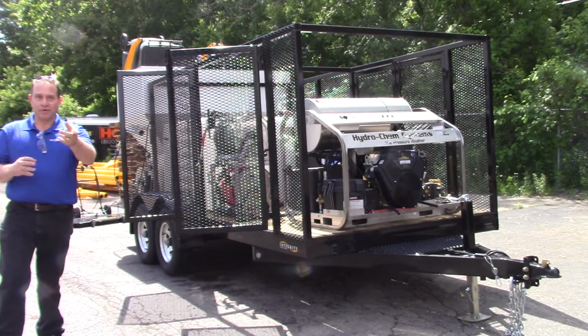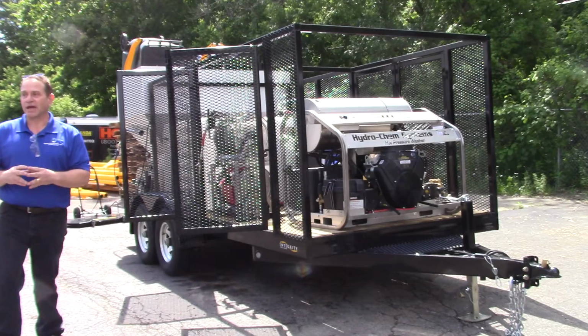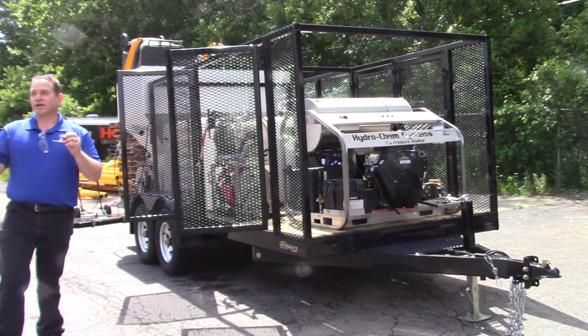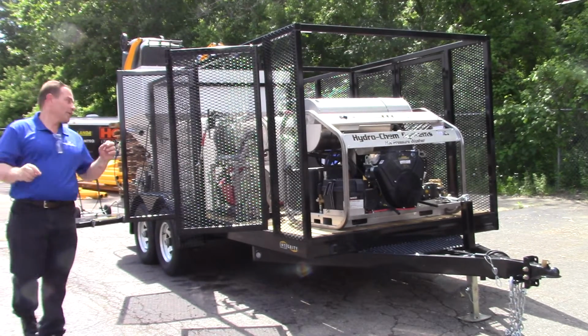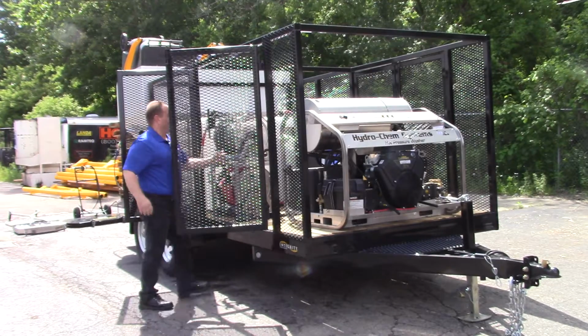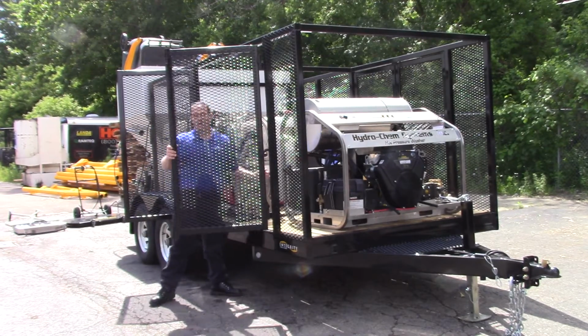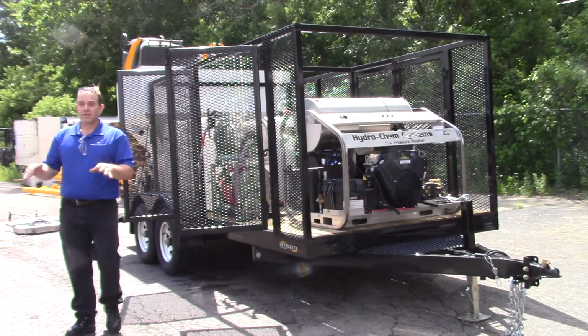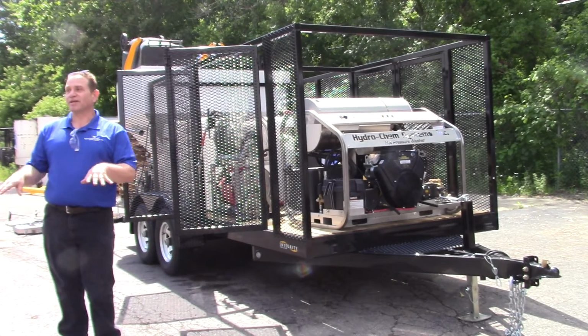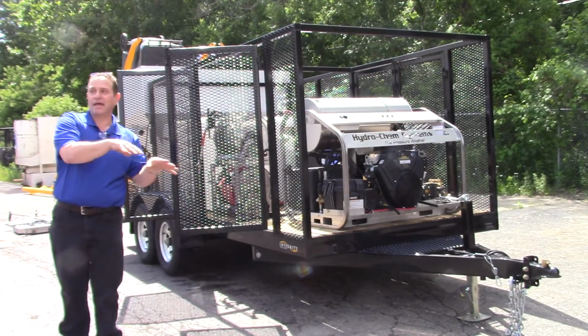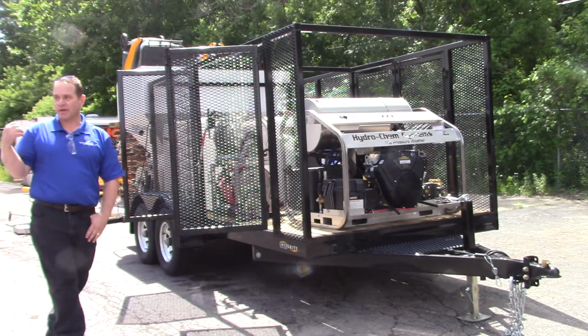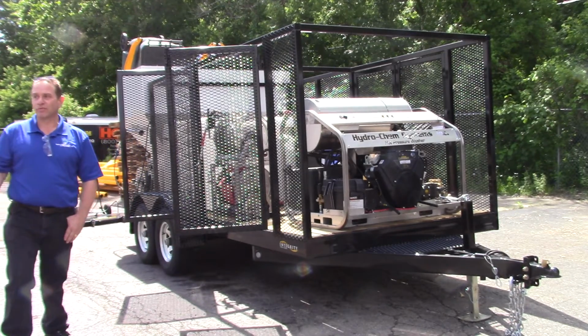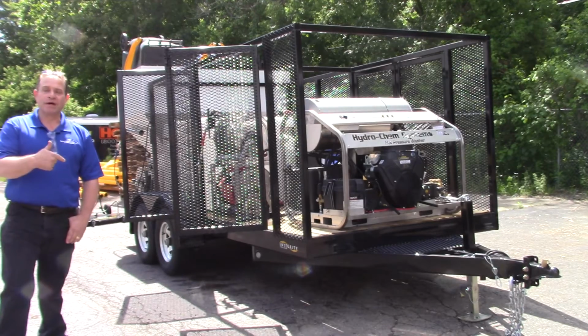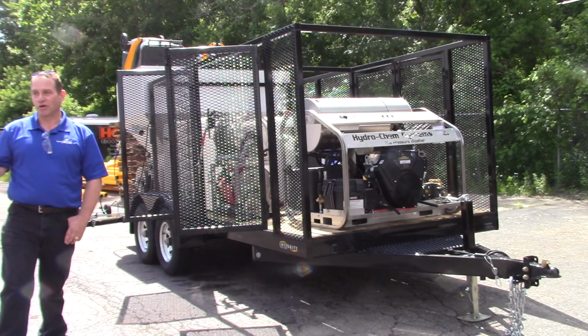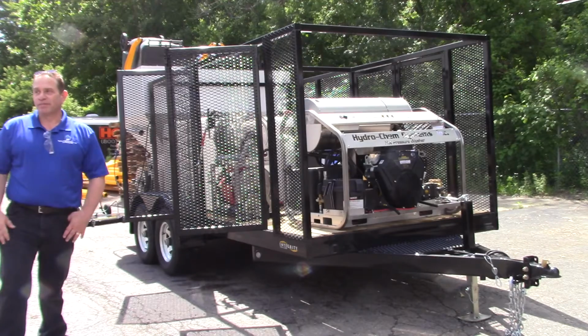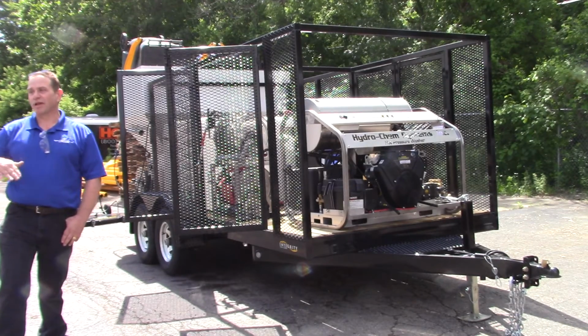So what I recommend, and we're going to put a spare parts kit together for all these guys, I've already sent them out. By having an additional steam burst relief valve, you're able to tell the customer, go ahead and reinstall the new burst valve, run it. If it blows off again, shut it down, take it to a service center. I have had that happen where it just popped off and never had another problem, and it wasn't really a big issue. But being that Hydrotech's owner owned the business at the time, he wanted to eliminate all the liability.